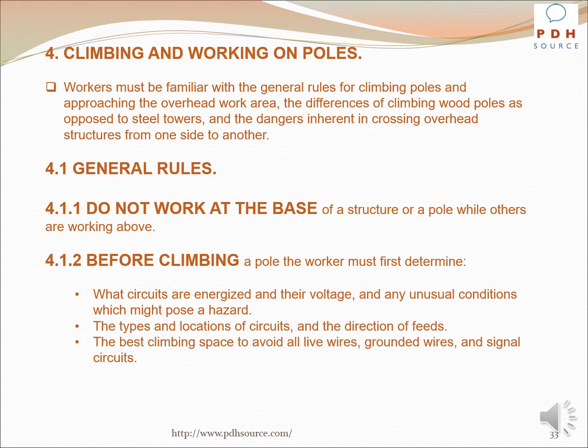Workers must be familiar with the general rules for climbing poles and approaching the overhead work area. The differences of climbing wood poles as opposed to steel towers and the dangers inherent in crossing overhead structures from one side to another. Do not work at the base of a structure or a pole while others are working above. Before climbing a pole, the worker must first determine what circuits are energized and their voltage, and any unusual conditions which might pose a hazard. The types and locations of circuits and the direction of feeds, the best climbing space to avoid all live wires, grounded wires, and signal circuits.